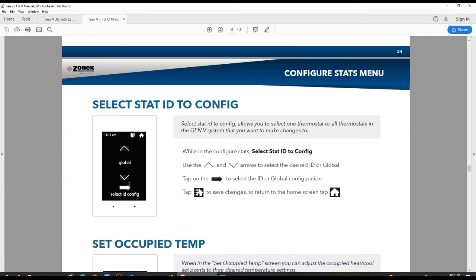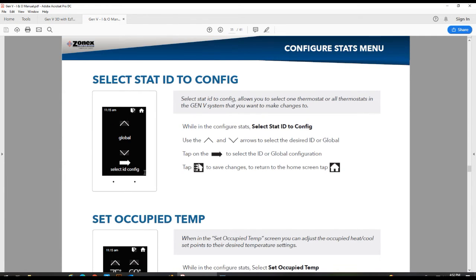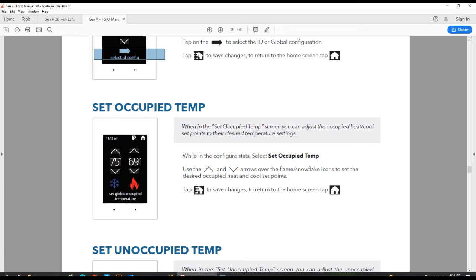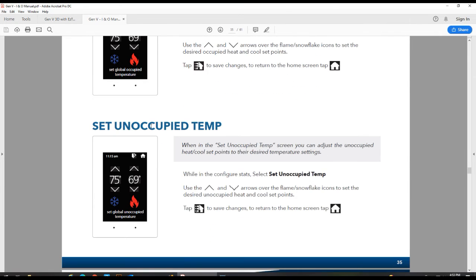So from your hub thermostat, when you select that Configure Stat option, you can go ahead and use the up and down arrows and select individual thermostats, or you can select the global feature. And to do that, you'll just use the down arrow, you'll drive past number 1, and it will say global. Once you see global, tap on the arrow to the right, and that will take you into the global configuration mode. Okay, once you're into the global configuration mode, go ahead and set the occupied temperatures you would like the system to operate at, as well as you can go ahead and set your unoccupied temperatures that you would like it to run at as well.